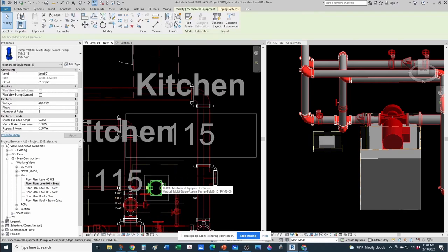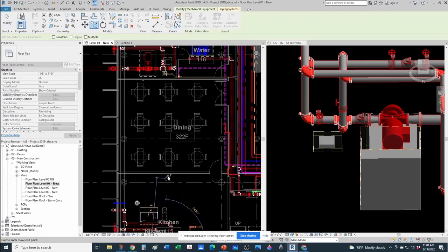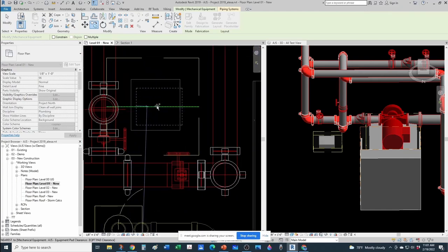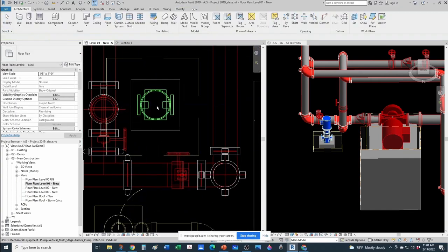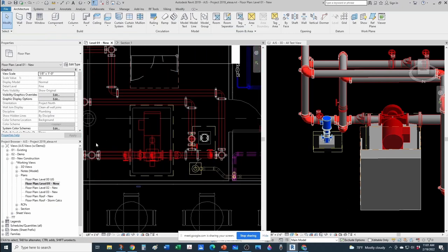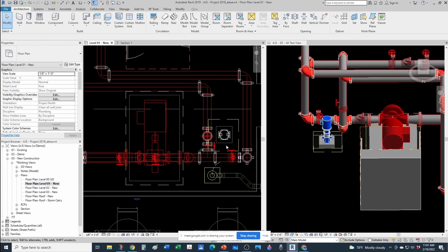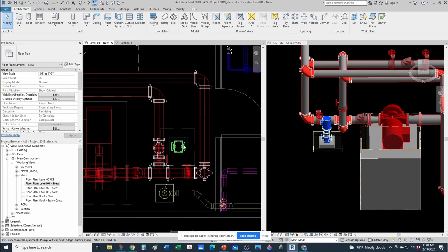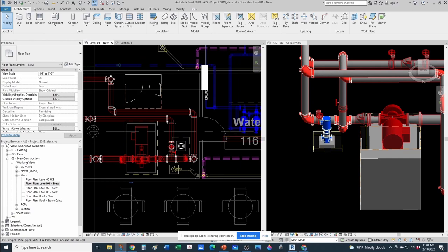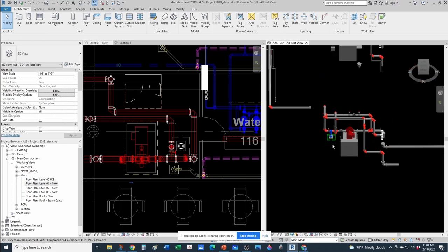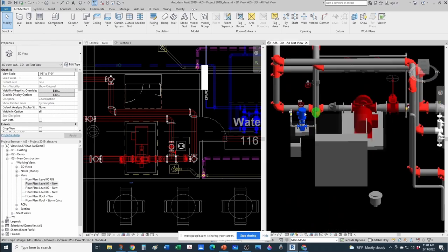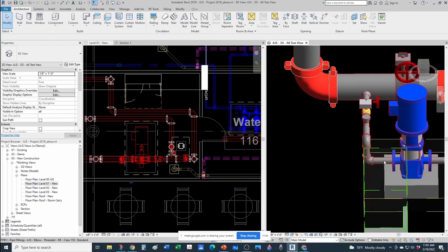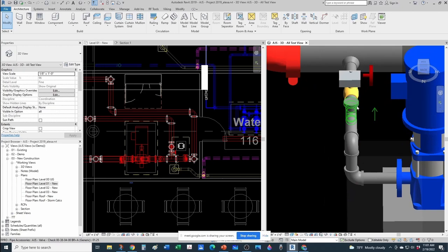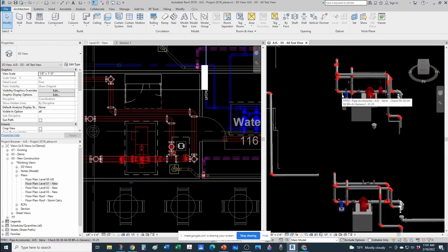So I'm going to do... I'm just gonna copy this one to save a little time because we're already at 11. We had a couple of hiccups at the beginning. So that would be our jockey pump, right? Then we need to connect suction to suction and discharge to discharge. Since these are small sizes, you want to use threaded pipe type. We also have a pipe type video on that, but if you see here in the one that is completed, it's coming out of the flange and it's just threaded, right? And then it has our check valve and our isolation valve.